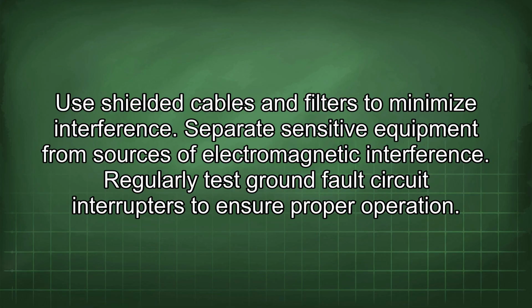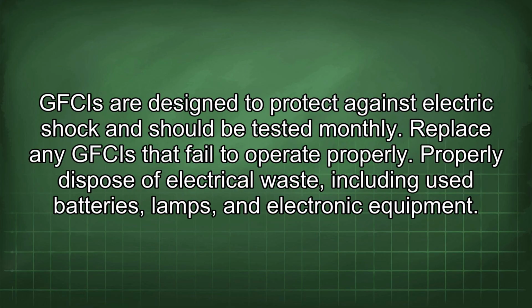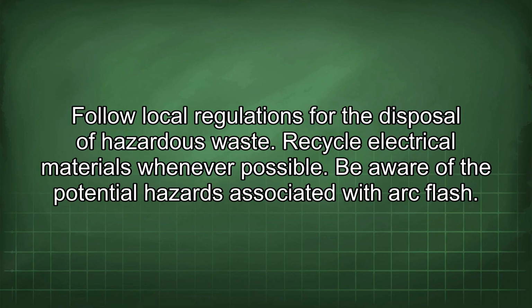Regularly test ground-fault circuit interrupters to ensure proper operation. GFCIs are designed to protect against electric shock and should be tested monthly. Replace any GFCIs that fail to operate properly. Properly dispose of electrical waste, including used batteries, lamps, and electronic equipment. Follow local regulations for the disposal of hazardous waste. Recycle electrical materials whenever possible.